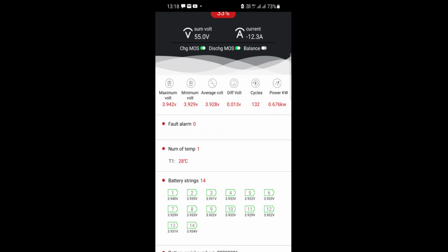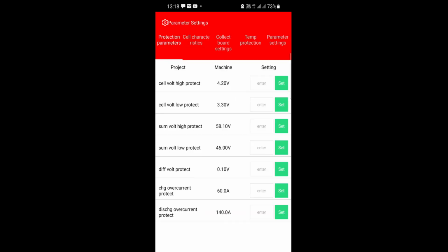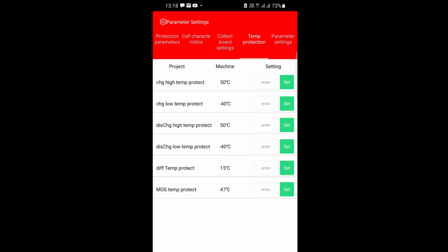You can also see the temperature T1 is showing as 28 degrees Celsius. There also, for high temperature, you can set a protection here. Go into temperature protection and charge high temperature protection. You can set it to some value. I have set it to 50 degrees Celsius. Charge low temperature you can also set. Discharge high temperature, discharge low temperature. Difference temperature protection is not applicable because we are using only one temperature sensor. And MOS temperature also you can set to a reasonable value.